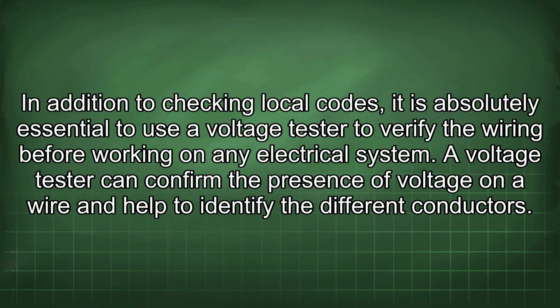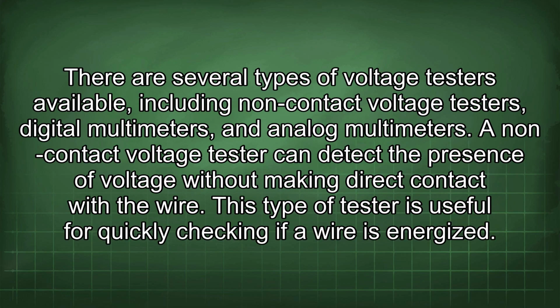In addition to checking local codes, it is absolutely essential to use a voltage tester to verify the wiring before working on any electrical system. A voltage tester can confirm the presence of voltage on a wire and help to identify the different conductors. There are several types of voltage testers available, including non-contact voltage testers, digital multimeters, and analog multimeters. A non-contact voltage tester can detect the presence of voltage without making direct contact with the wire. This type of tester is useful for quickly checking if a wire is energized.